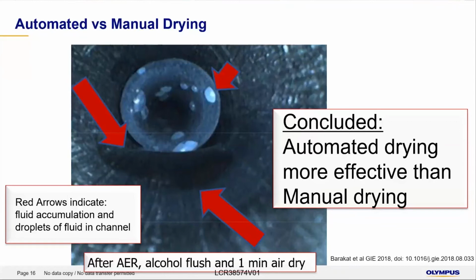And if you can go to the image that you're seeing right now, this was a study that was done by Barakat. Basically what we're looking at is down the instrument channel through the biopsy port. This was an endoscope that was used on a patient. It was fully manual, bedside pre-cleaned, fully manually cleaned, and then reprocessed through an AER, and the alcohol flush and air flush were done. You can see the red arrows point out the residual moisture that is in the channel. So this is a scope that's just come out of an AER, and it shows you how much moisture there actually is in the instrument channel.